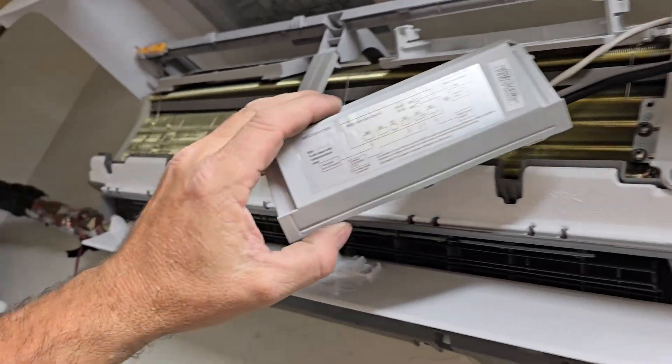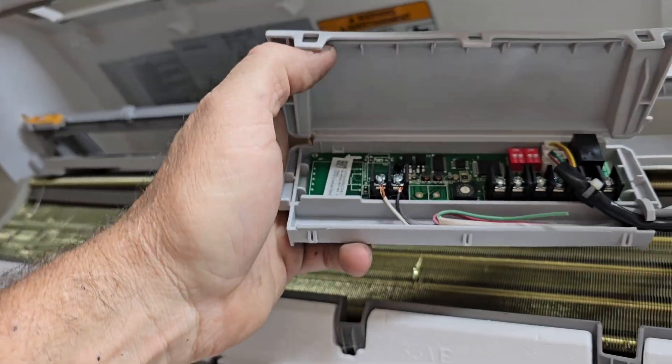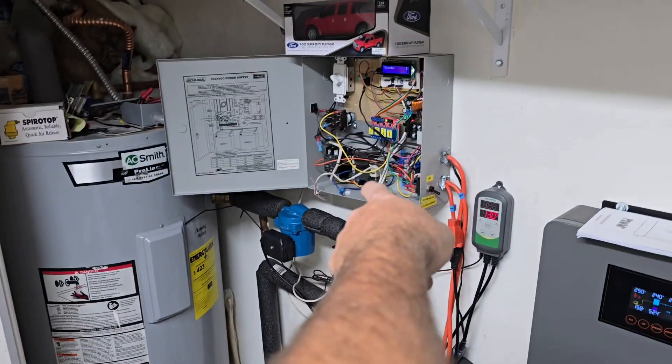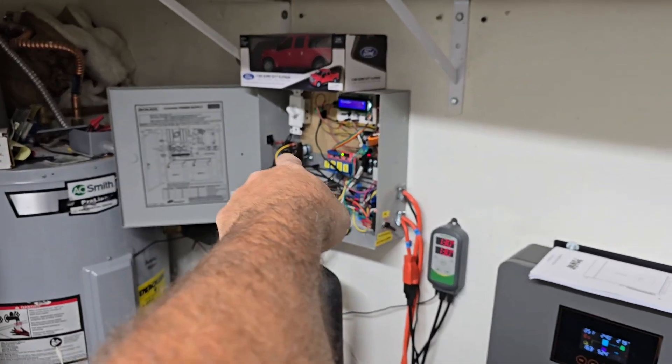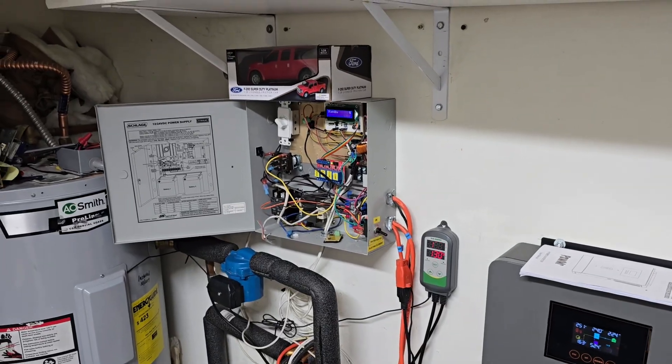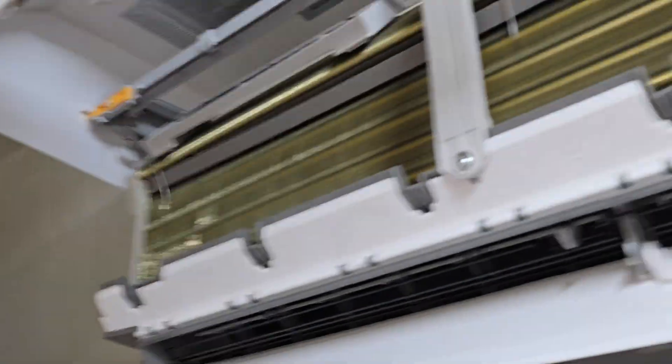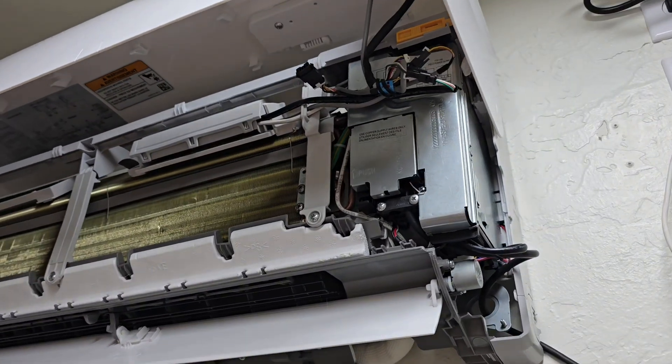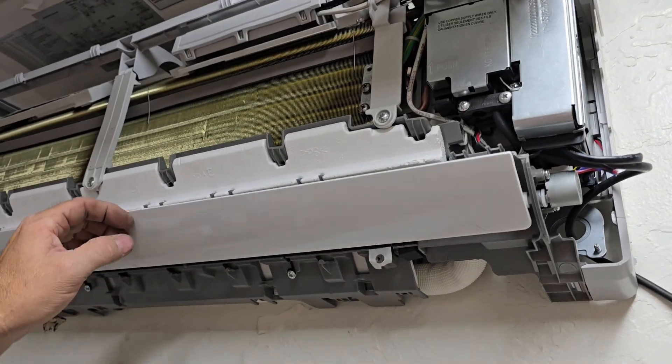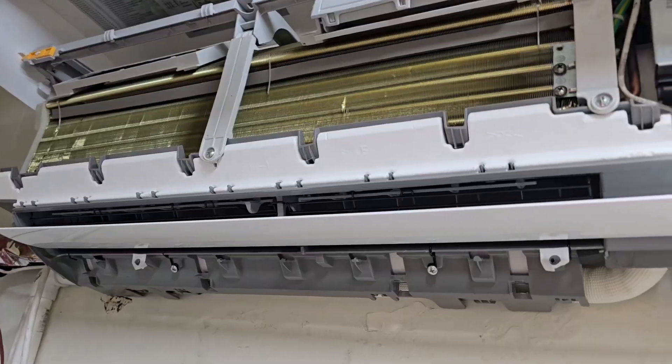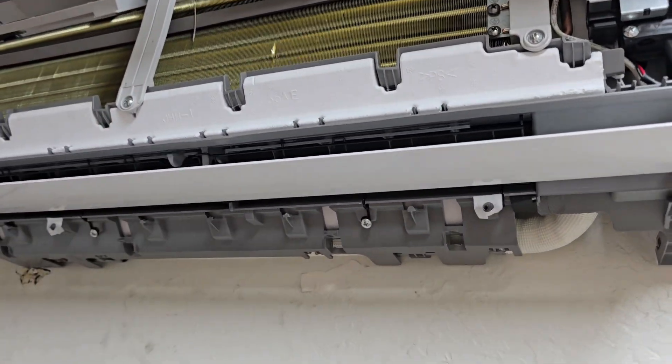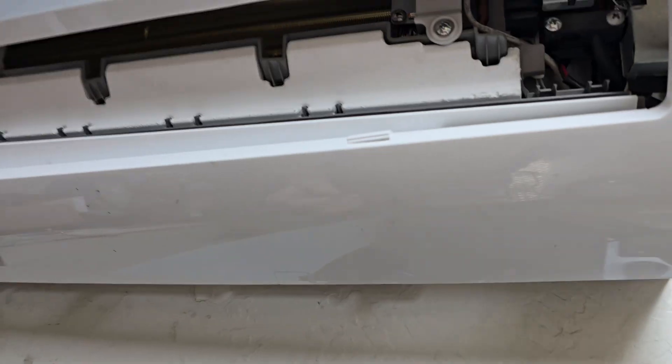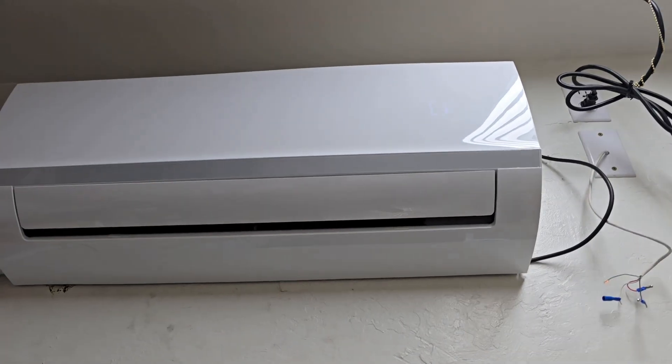I got this unit kind of hung, just a thermostat that's not connected now, got the remote attached to that, and that wire is to already go down the line sets and come out over there. I just checked it, continuity is good. Extra contact on the relay over there that starts stops that little baby 6000 BTU compressor out there. I'll just apply those to those contacts and I'll start stop the fan over here. This is a pretty cool high wall unit that had the kickstands to hold it up while you're connecting the lines, and then you collapse them and it drops. Up here it's got these little things to hold this open.